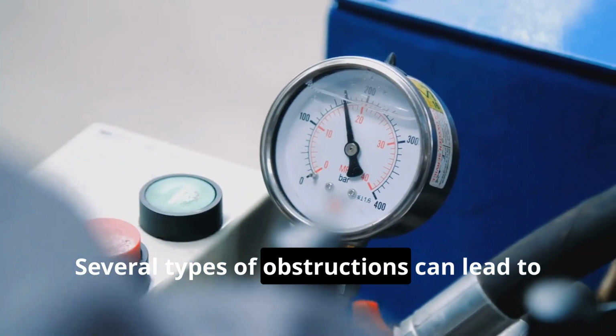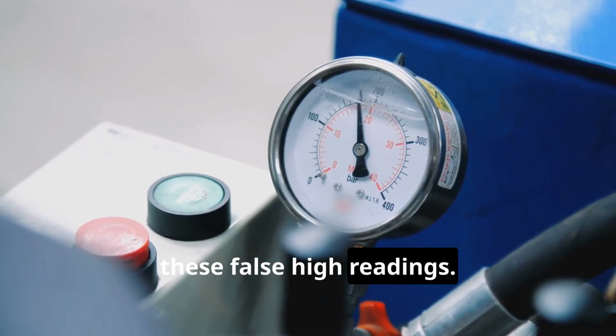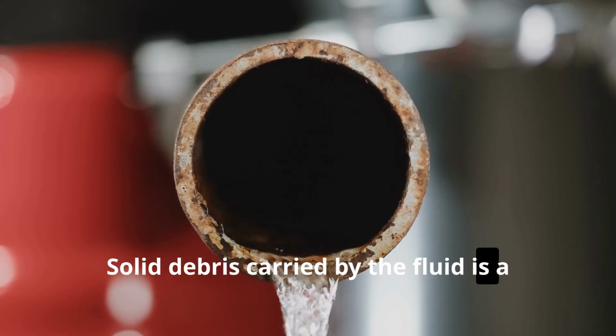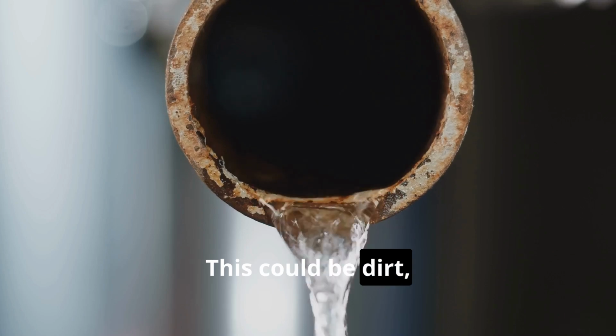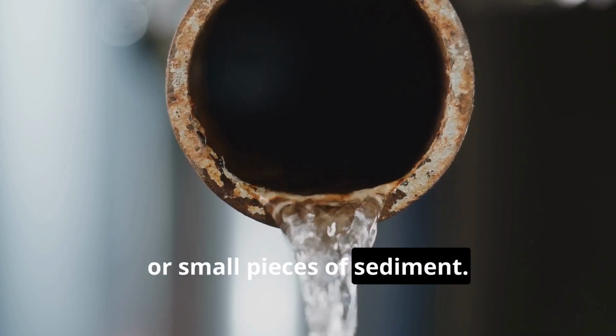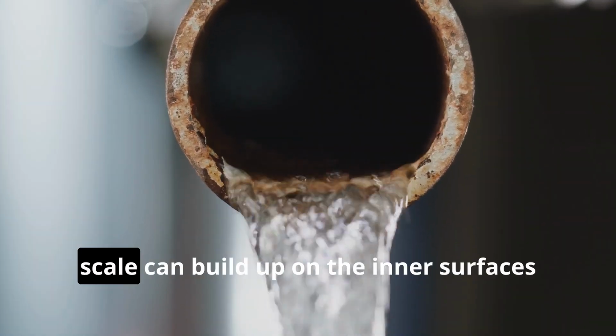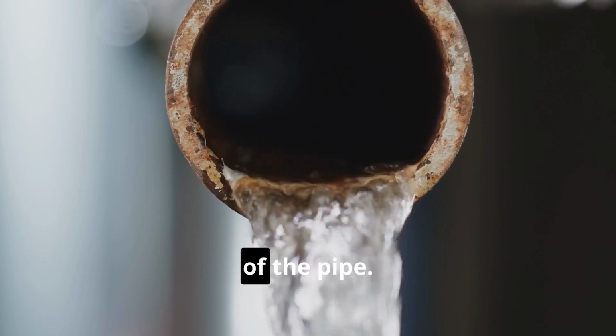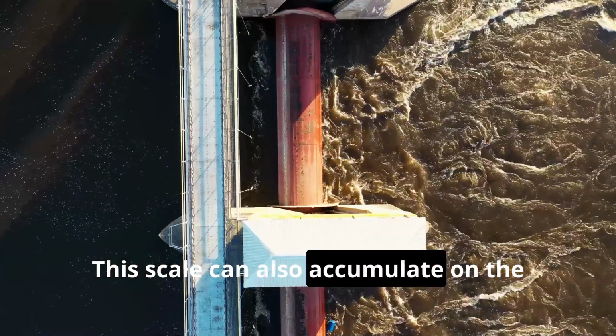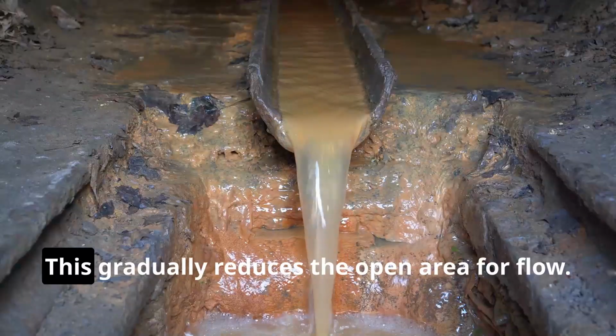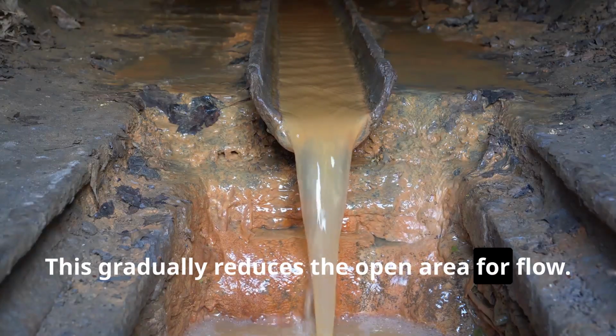Several types of obstructions can lead to these false high readings. Solid debris carried by the fluid is a common culprit. This could be dirt, rust particles, or small pieces of sediment. In some processes, scale can build up on the inner surfaces of the pipe. This scale can also accumulate on the primary flow element. This gradually reduces the open area for flow.